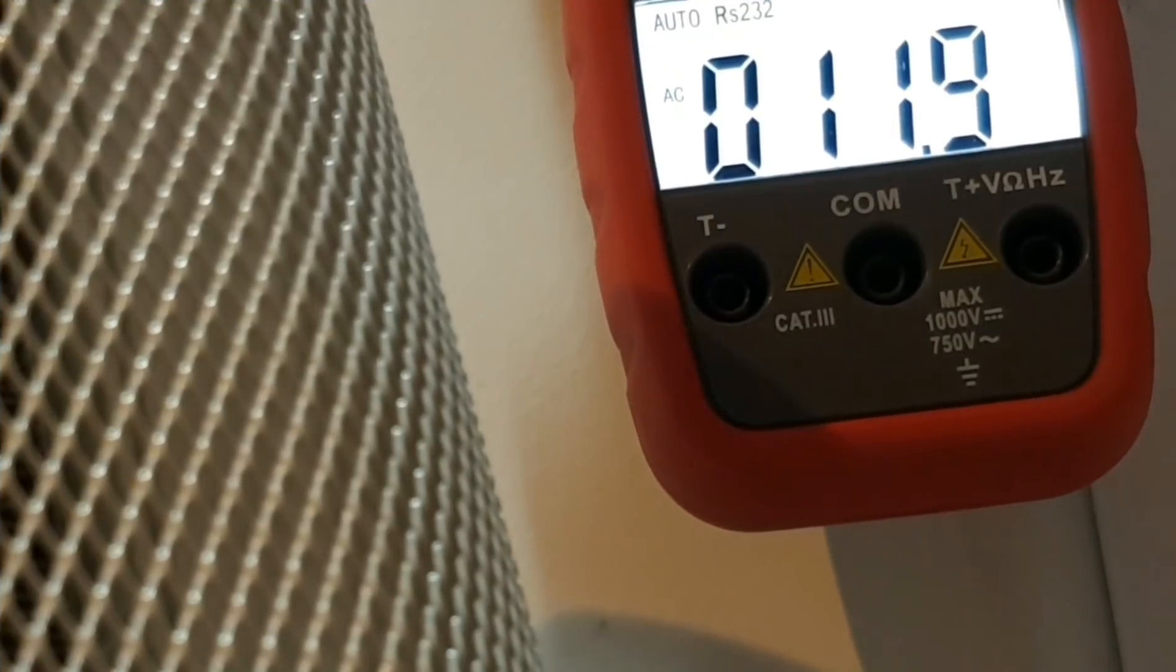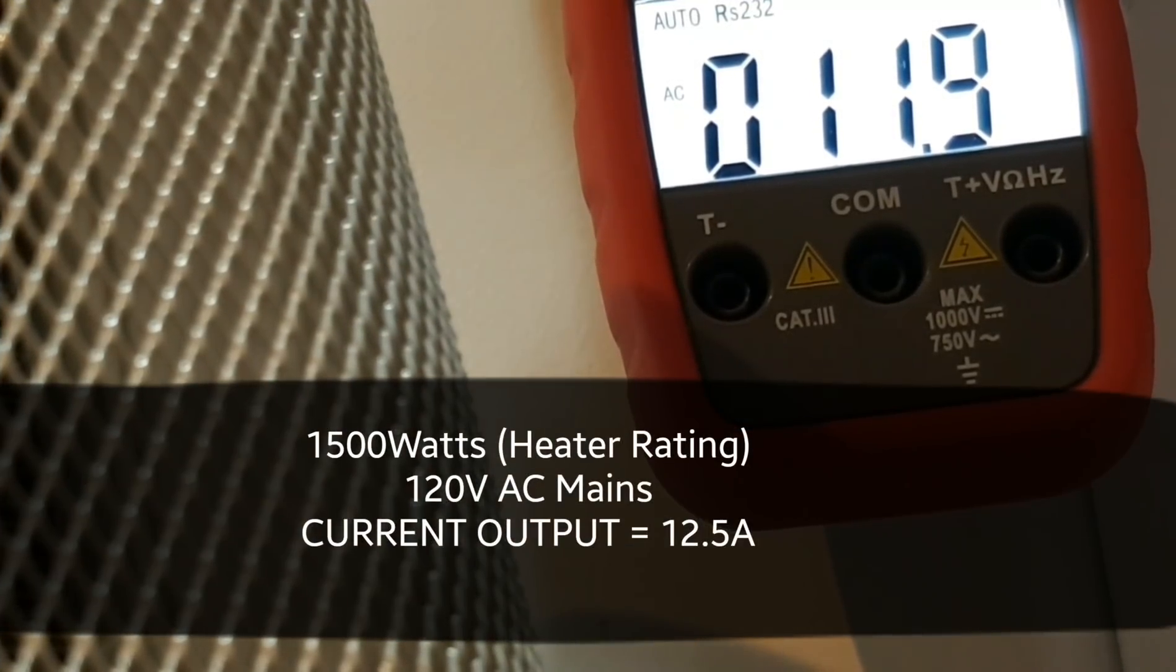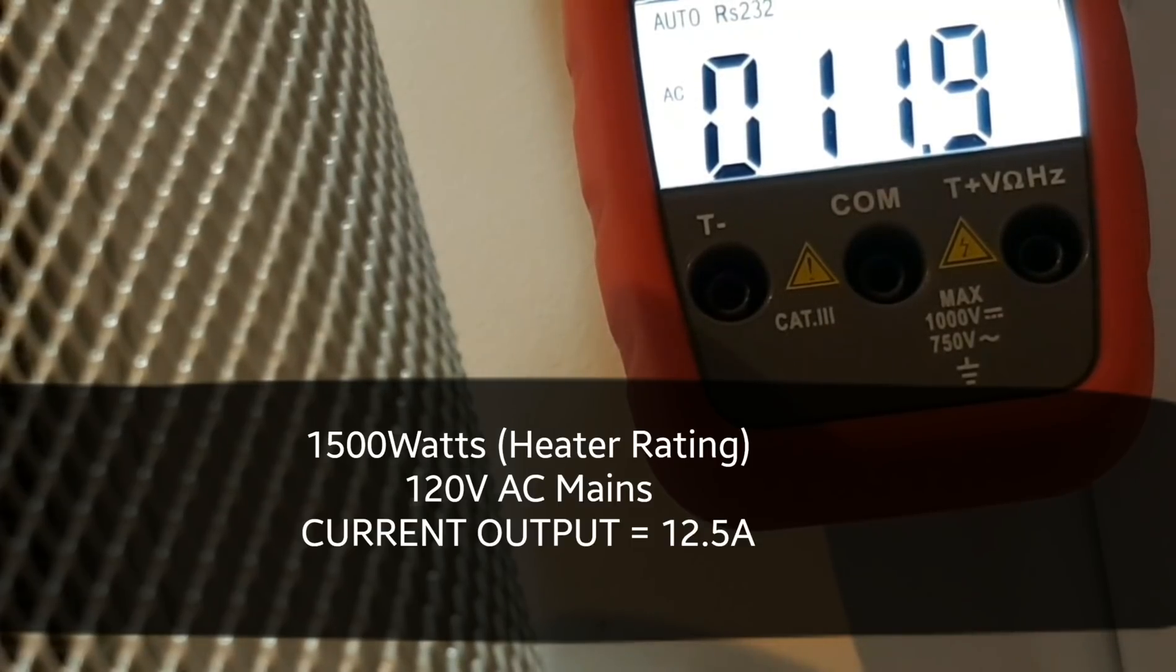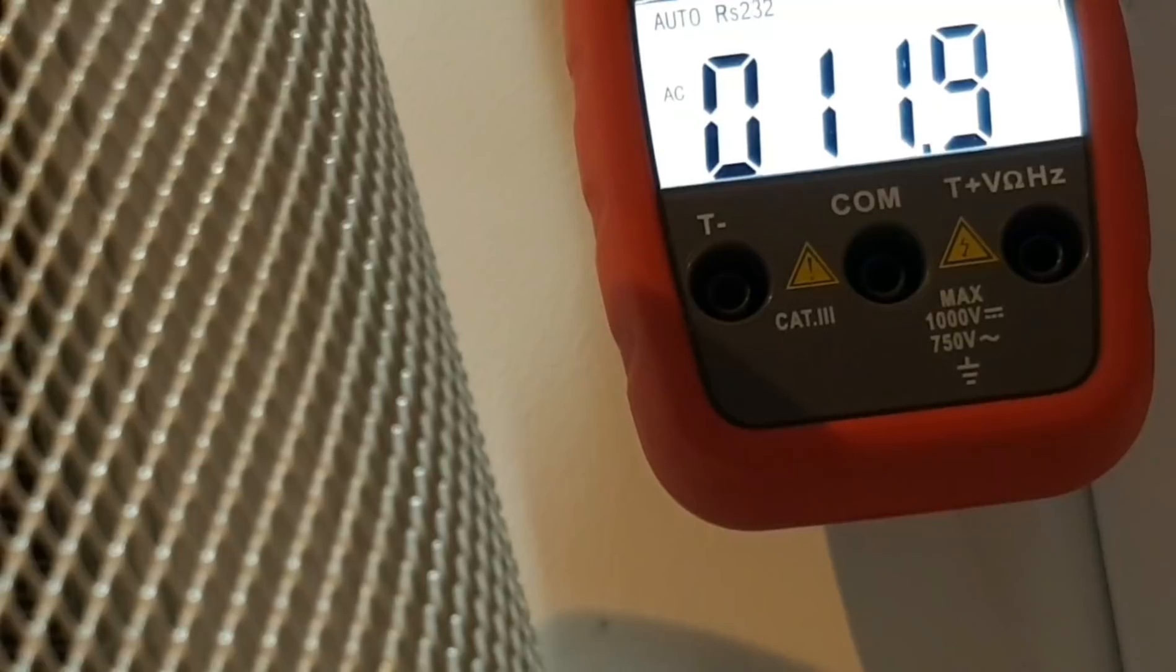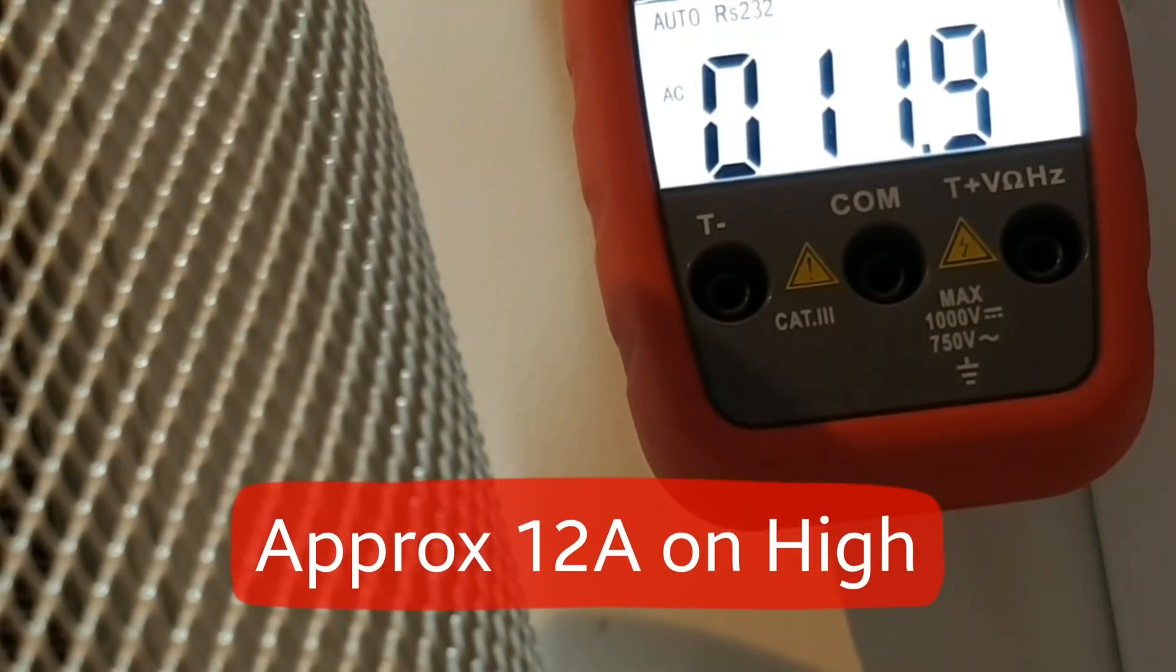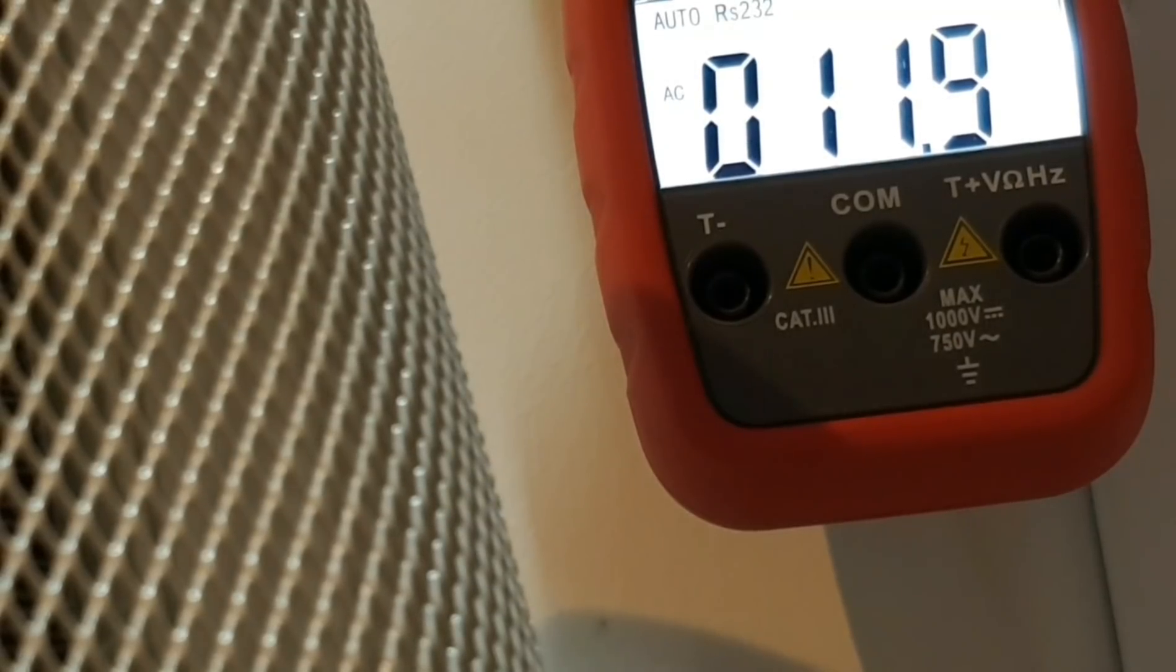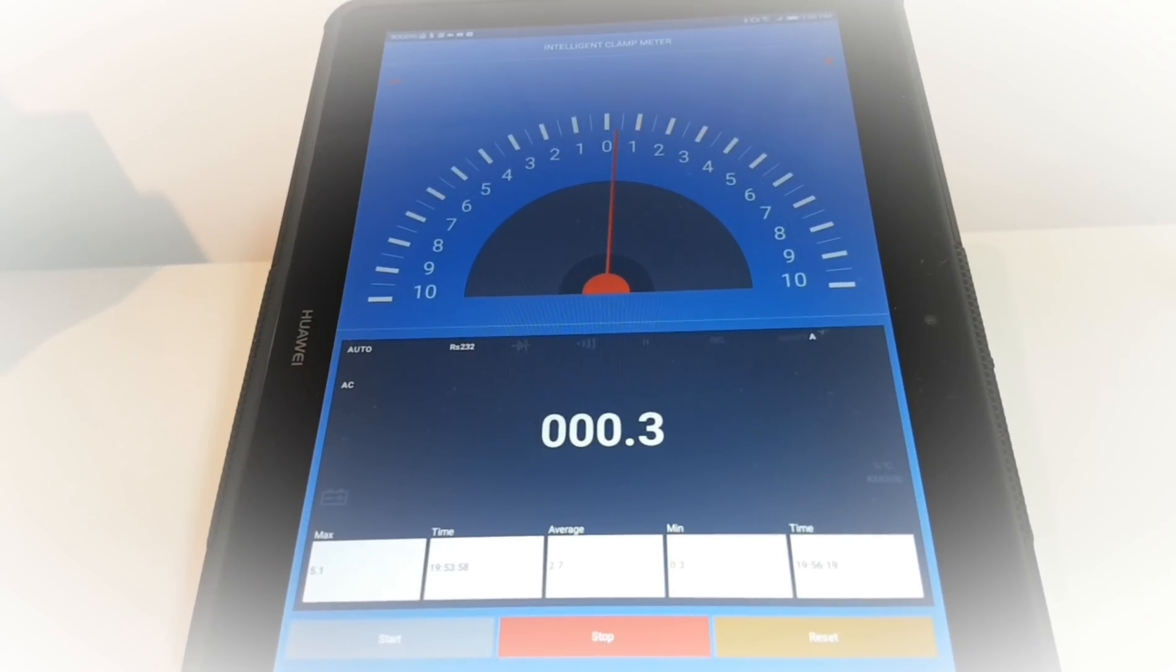So if we convert watts and volts to amps, if we do the math quickly, let's see: 1500 watts, the voltage here in Canada is 120 volts, and the result of that is a current output of 12.5 amps or 12,500 milliamps. And as you can see we are definitely very close to that, so we know that this heater is running as per norm and everything is a go.